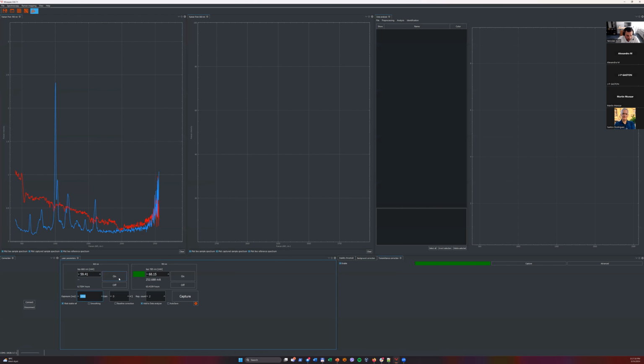Then I can switch to the 660 nanometer laser. And again, here we see the signal from the inbuilt reference sample. Basically what the device is doing, because the small lasers which we use are not thermoelectrically cooled, because you cannot put cooling like that in a small package like this. And because this is supposed to be battery powered, the lasers are drifting around and mode hopping, but everything is compensated when we look at the reference channel. So basically everything is stabilized, because we know that in the reference channel we have a polystyrene sample, and then the embedded software is performing all these corrections and calibrations in real time.